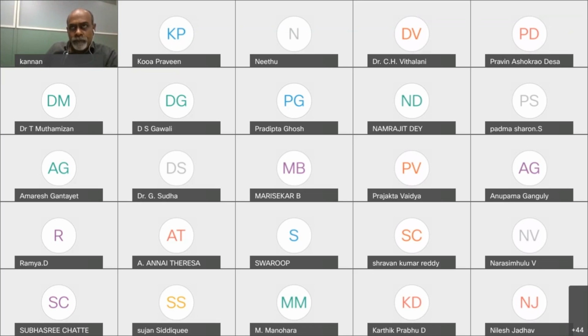So if you understand what we just now discussed about the solver, you have understood the entire algorithm of the controller. There is nothing more to it. Only if you come to the special category of motors called IPMSM, then there is one more algorithm which will be used in certain operating conditions. We will discuss that a little later. But I'm spending a lot of time because I have practically covered the entire motor control software which is applicable to 80% of the motors that are used. So if you have any doubt about this, please ask me. It's a very important thing.